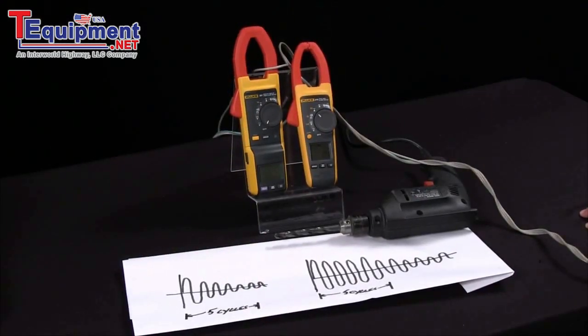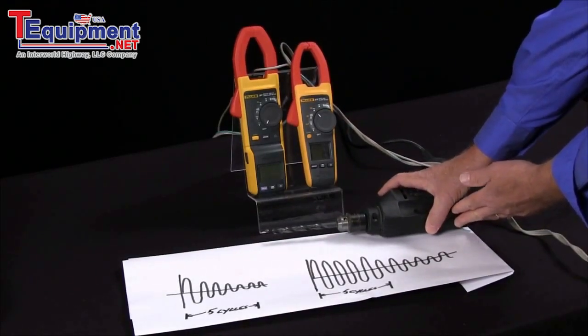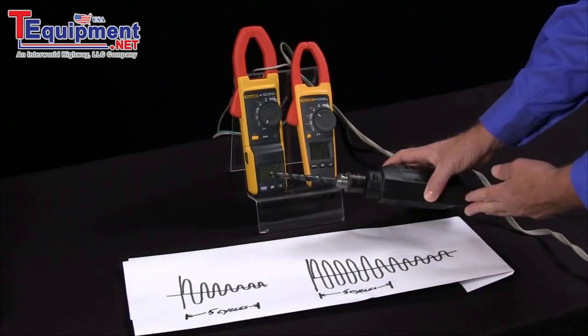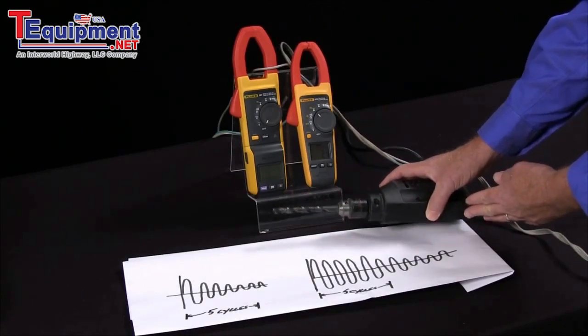What is inrush current and why is it important to be able to measure that? Well, inrush current on a motor is sometimes called the starting current or the locked rotor current, and this will increase as our device starts to age or our bearings need grease. It's also important to know how to do this so we can right size our transformers.